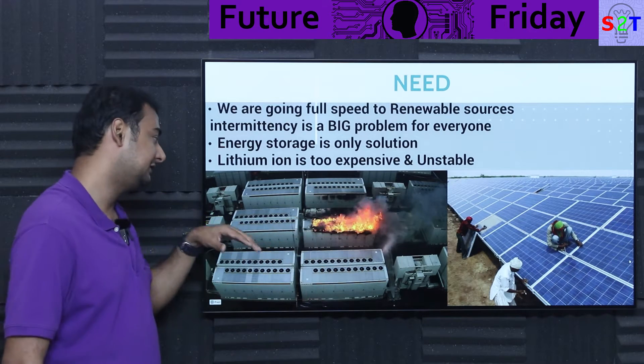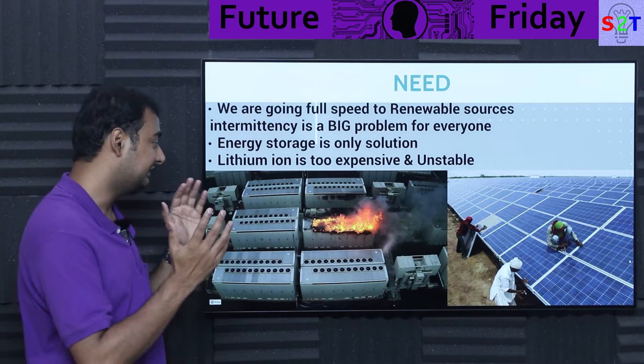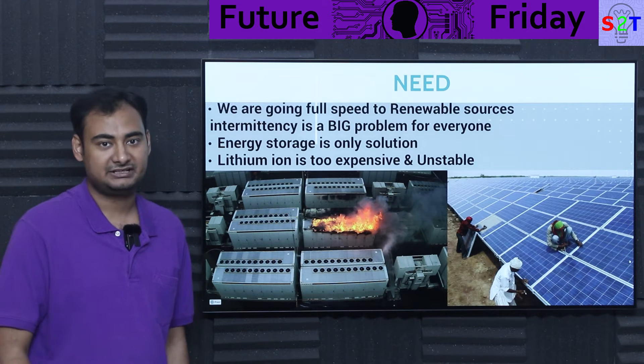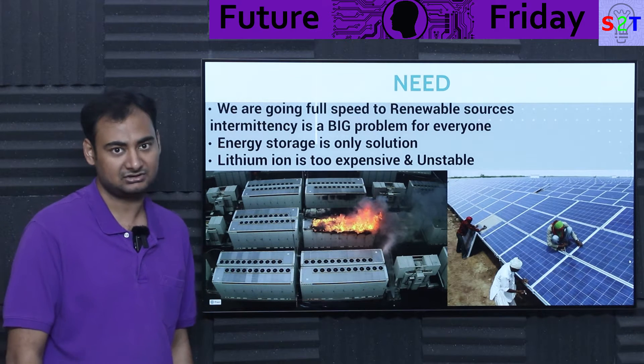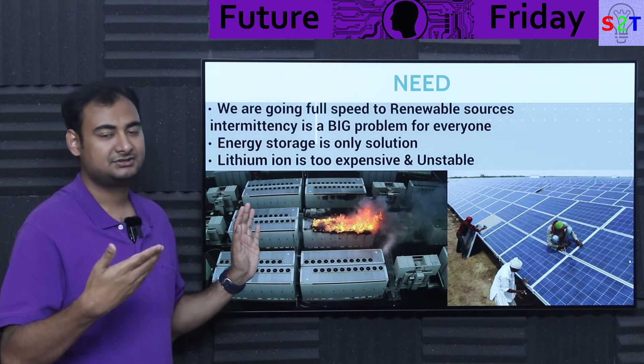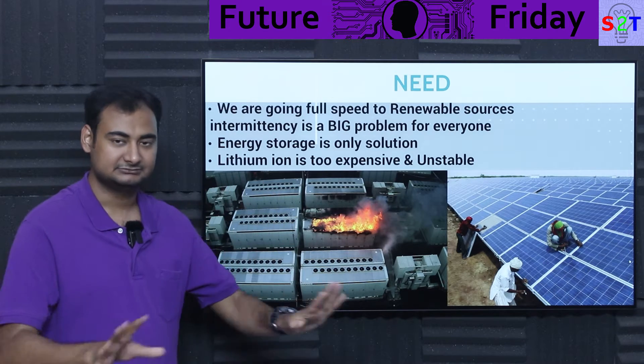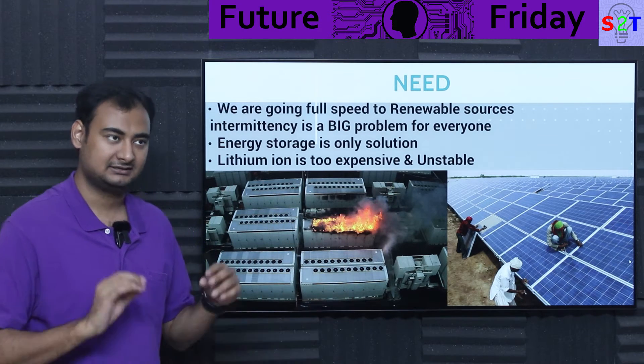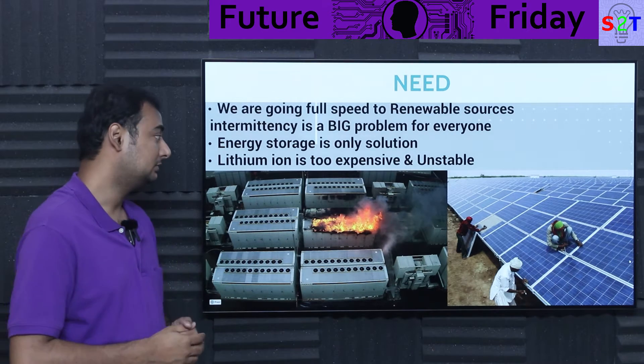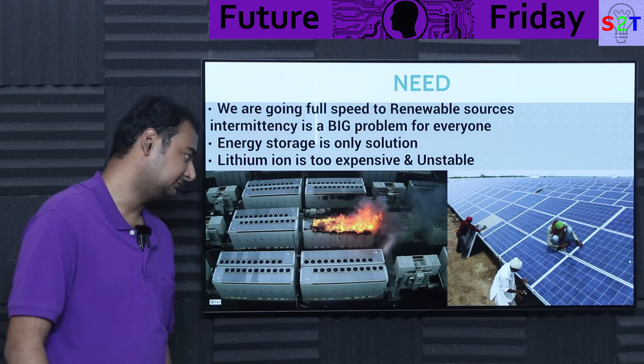Lithium-ion is also unstable. If you're talking about India or Australia, when you're using lithium-ion you have to have an air conditioning unit running on them. Otherwise, cell temperature could go ludicrously high because outside temperature in those areas can easily cross 50 degrees Celsius. At that point you are losing energy to inefficiency. We have to use cooling systems, which adds parasitic losses. So overall, it's just the only option we have right now at large enough scale.